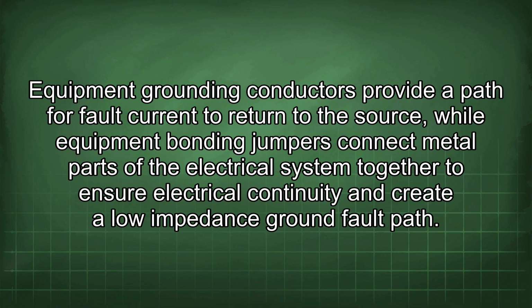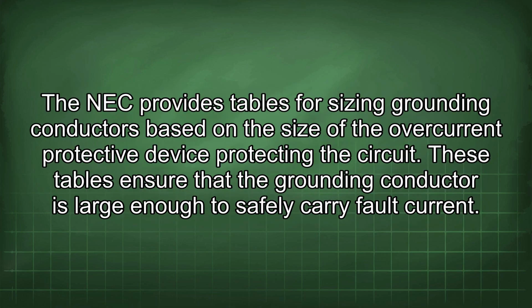Equipment grounding conductors provide a path for fault current to return to the source, while equipment bonding jumpers connect metal parts of the electrical system together to ensure electrical continuity and create a low-impedance ground fault path. The NEC provides tables for sizing grounding conductors based on the size of the overcurrent protective device protecting the circuit. These tables ensure that the grounding conductor is large enough to safely carry fault current.